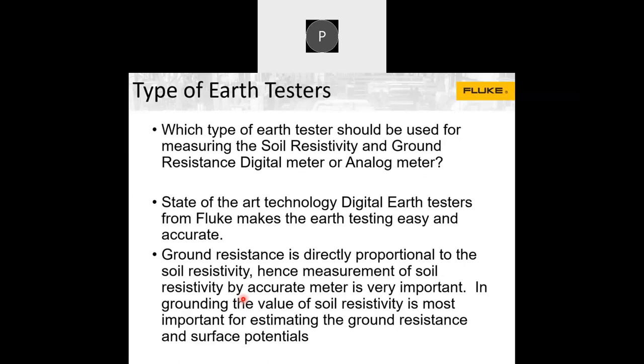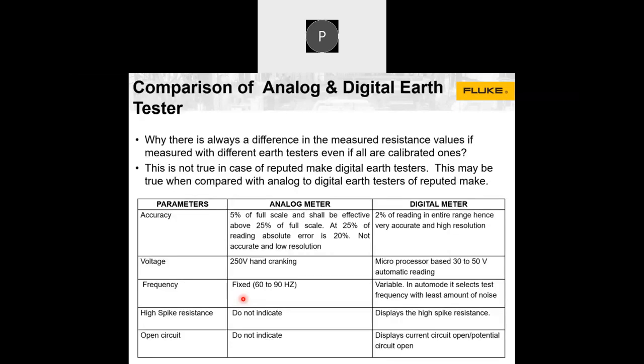Especially for critical applications and communication systems, people recommend resistance values very close to 2 ohms or less. Some applications may require 5 ohms or less. In calibration laboratories, it may need to be 1 ohm or less in the electrical grounding systems. What happens when you use these products, whether analog type or very low cost type? Here's a quick comparison of analog meters and digital meters.